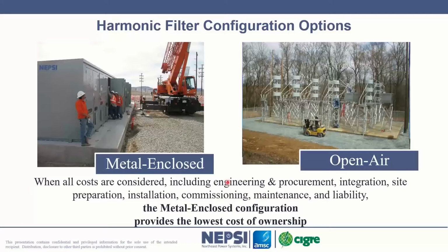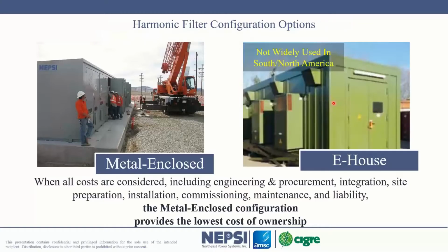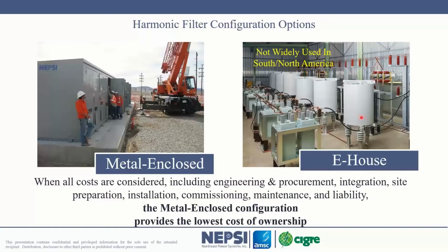Here's another example of a harmonic filter that's air core on the right. Here you can see we have 5 stacks of reactors, stacked up, 5 of them. You can see the resistor cages here developing the harmonic filter branches. So again, air core reactors. There's also an E-house type solution, and also another very common way of doing harmonic filters, and that is to take an E-house and put the reactors, capacitors, and resistors into the E-house, put some air conditioning on the side, and you have yourself a harmonic filter also. So another way of doing it. It's not something that's used too widely in North America or South America, but it is certainly used in other parts of the world. And this is how that solution looks on the inside. And incidentally, this E-house solution shows air core reactors, but many E-house solutions use iron core reactors.